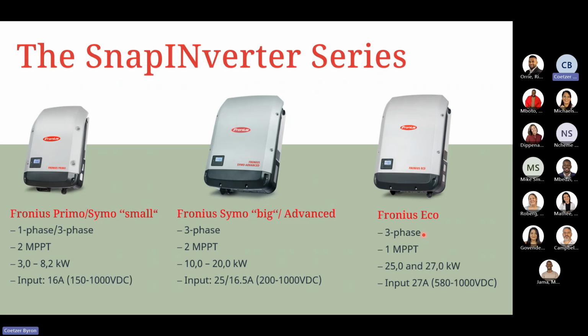Lastly, on the Snap inverter range is the Fronius Eco unit. So this is again a three-phase. You got a single MPPT input on the unit, and then power class 25 or 27. But most commonly the 27 kilowatt is available in the country. And this has an input range of 27 amps and then 580 to 1000 volt DC.